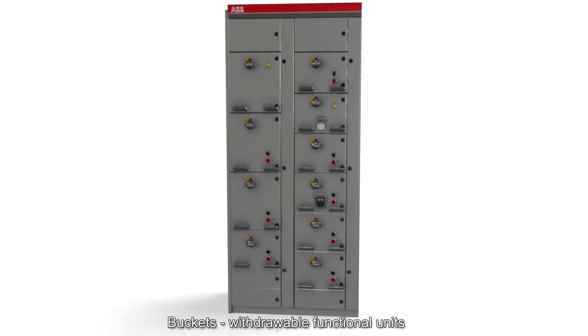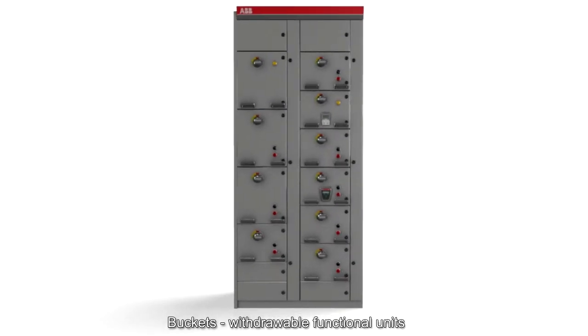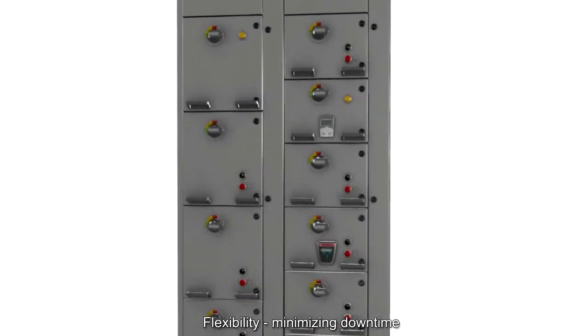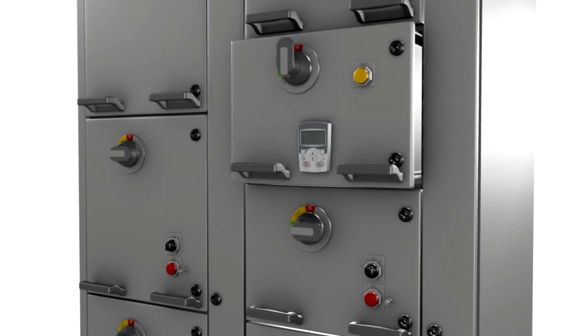Buckets, the withdrawable functional units, such as motor starters, contain the main power circuit along with electrical control and protection devices. To achieve the greatest possible flexibility and minimum factory downtime, the MNS MCC Motor Control Center offers plug-in, withdrawable, and full-height vertical options for incoming and outgoing units.